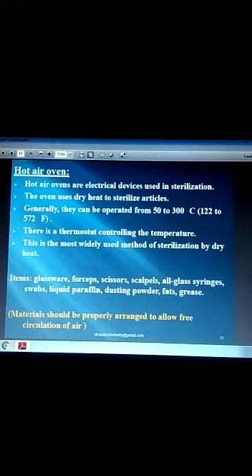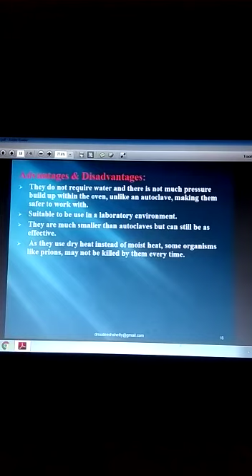What are the items which are sterilized? Glassware, forceps, scissors, scalpels, all-glass syringes, swabs, liquid paraffin, dusting powders, fats, grease, etc. This is the hot air oven instrument, used for sterilization. What are the advantages? They do not require water and do not need much pressure. Suitable to be used in a laboratory environment. They are much smaller than autoclaves but can still be as effective.